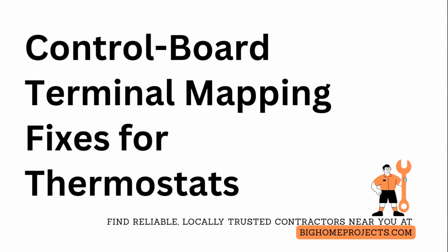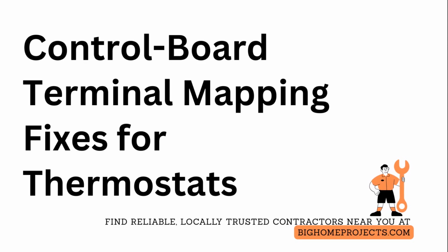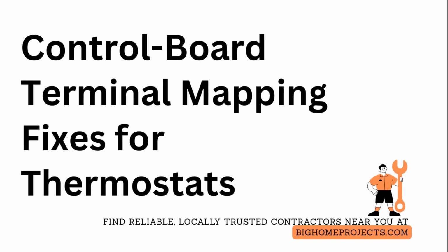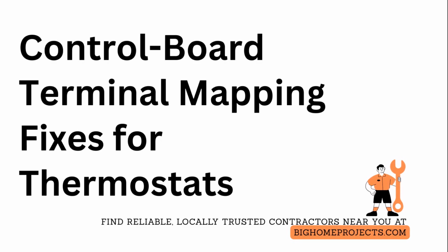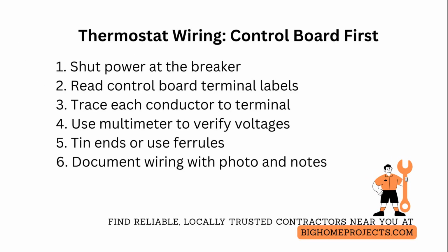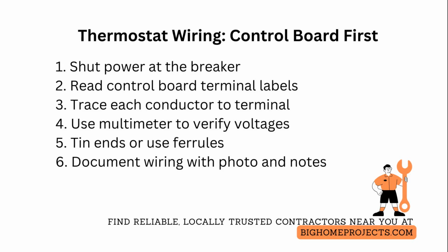Upgrade your thermostat wiring confidently by first treating the furnace or air handler control board as the authoritative source for every wire's function and termination. When replacing or installing a thermostat, start by shutting power at the breaker and removing the furnace or air handler service panel to expose the control board.